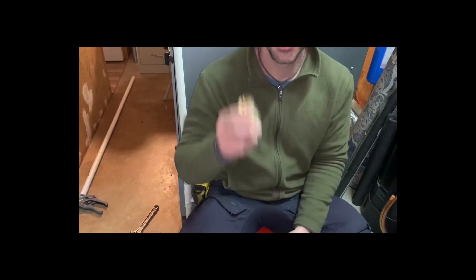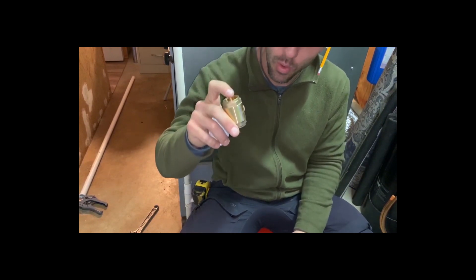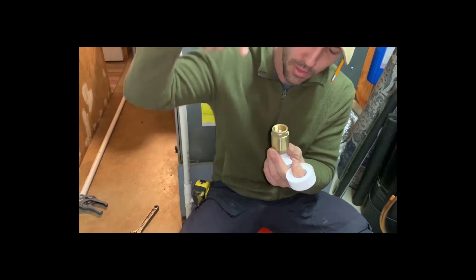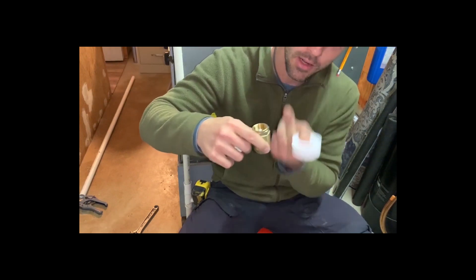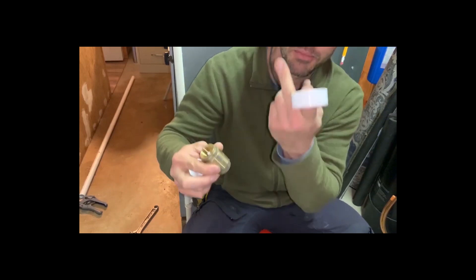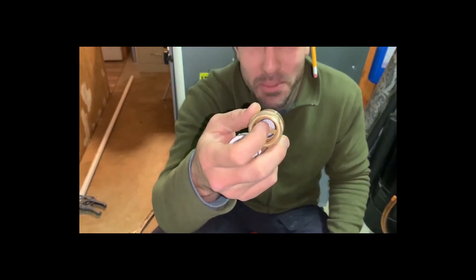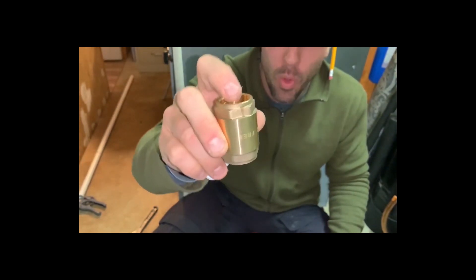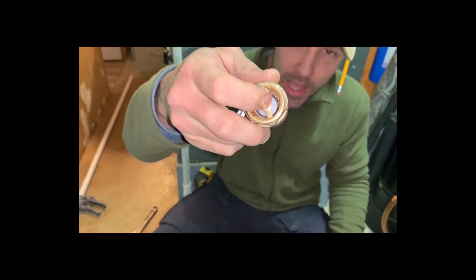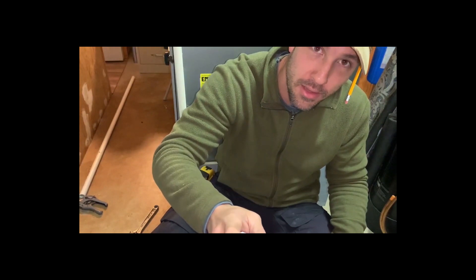I've also got to install a check valve. This check valve allows water to flow in only one direction—it's going to flow through the check valve this way, but it can't go back this way. It's got a spring-loaded little piston kind of valve in there, and the water pressure as I pump will open it up and then it will spring back and close it so the water can't flow backwards back towards the well.